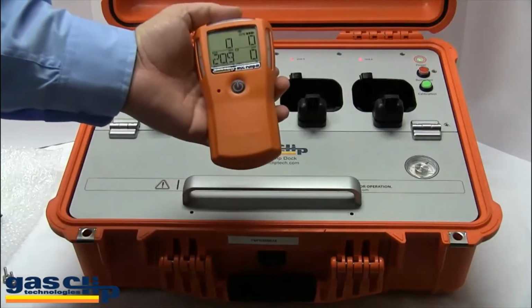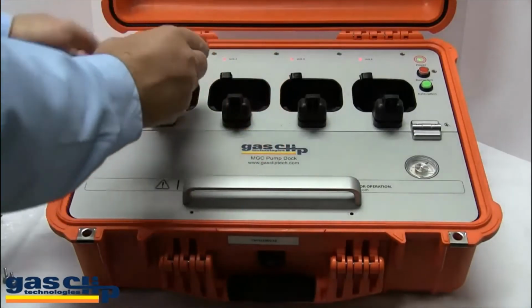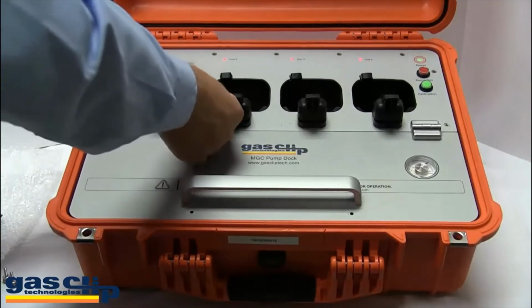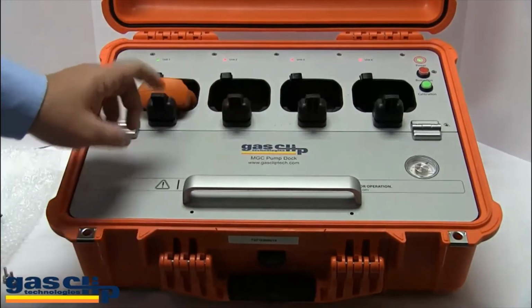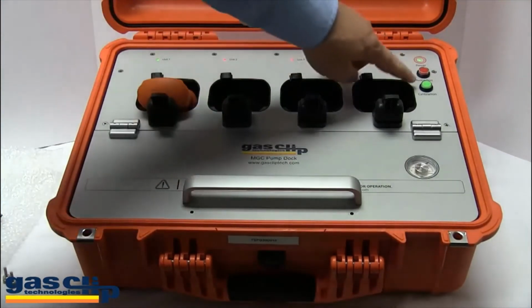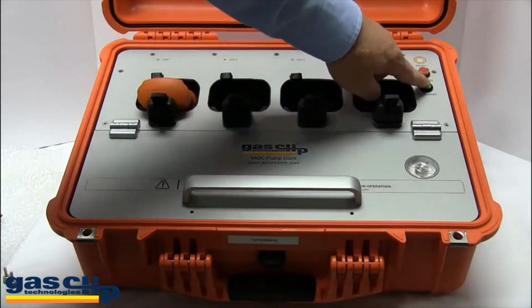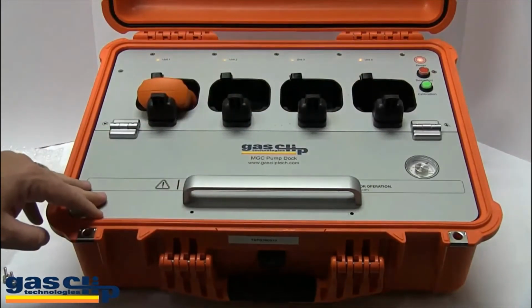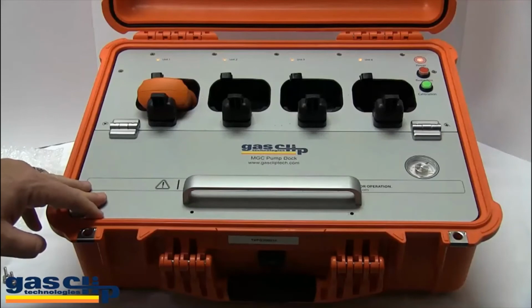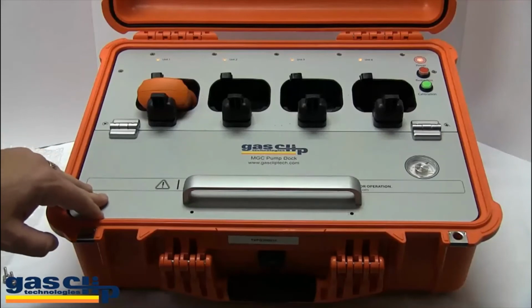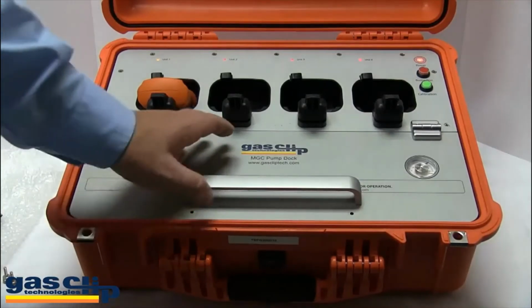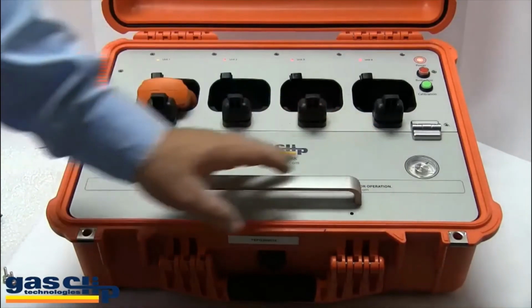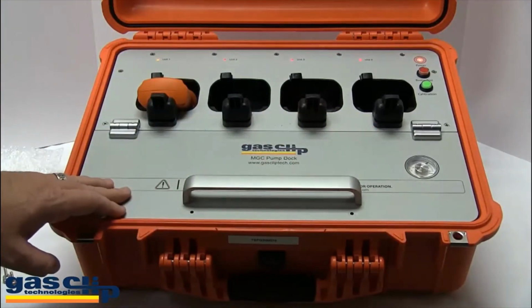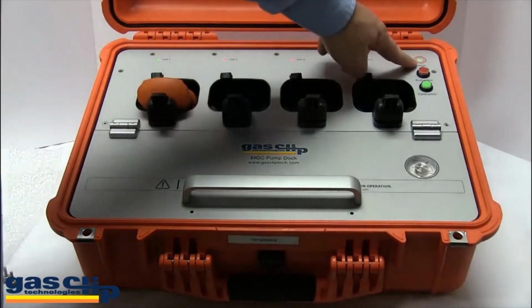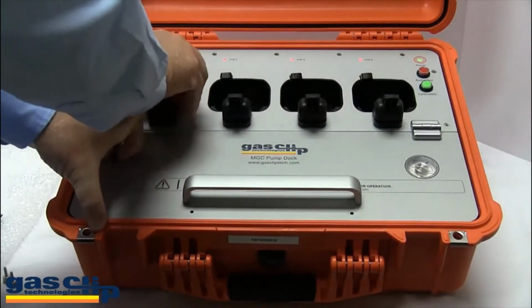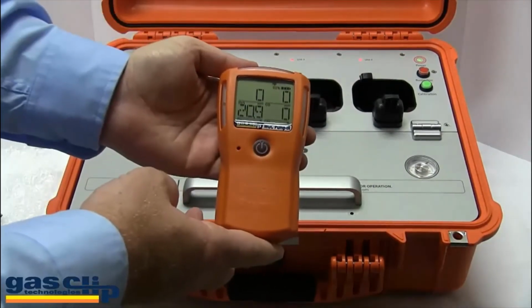To perform a calibration test, place the monitor head down in the docking station and secure underneath the clip. Press the green button for calibration and it will perform the test just like the bump test. However, please note that calibration takes about 1.5 minutes to do, regardless if you have 1 or 4 monitors in the docking station at the same time. The light is green, the monitor has been successfully calibrated and is now ready for field use.